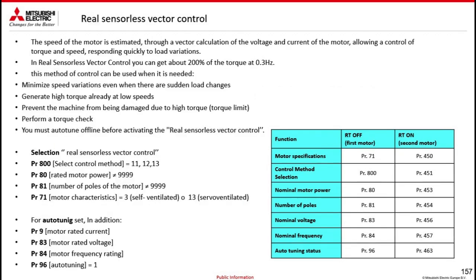Then we move on to the real sensorless vector control. This type of control is only available for FR-E800 and FR-A800 inverters. I get 200% of torque at 0.3 Hz, very efficient in terms of control methodology. The procedure is always the same. I do the auto-tuning in advanced mode, and then I change a parameter. The parameter 800, which changes the control methodology. By changing that, I tell the inverter you will now work in real sensorless vector control.